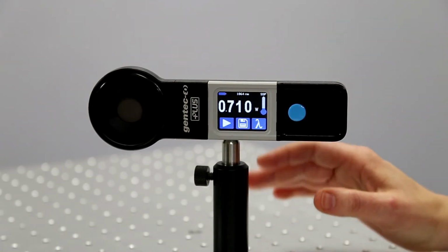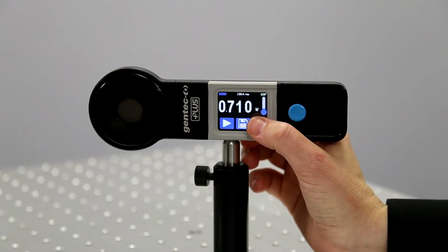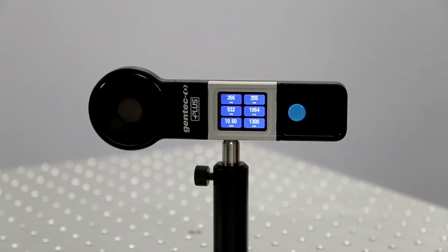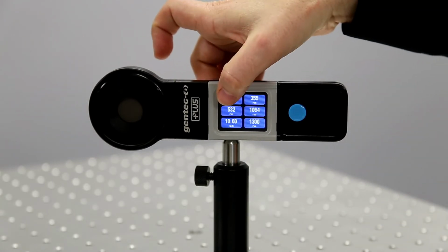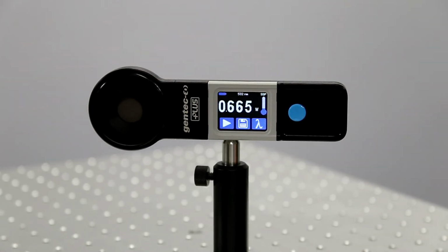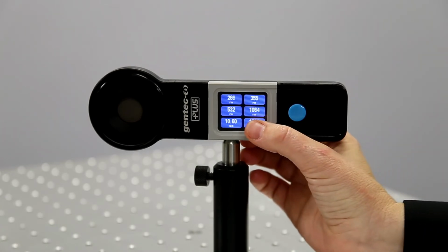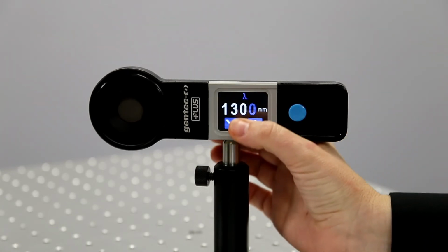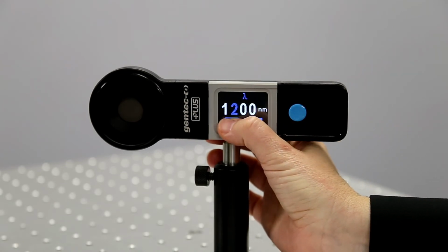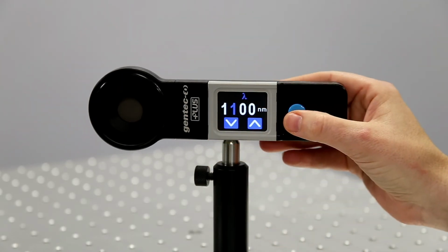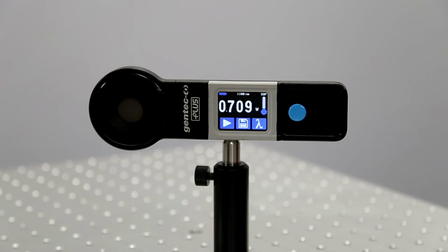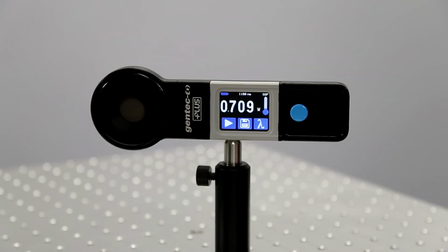To change this, you first tap on the button with the wavelength symbol, which brings you to a screen with 6 preset values. If there's one that you like in there, you can simply press it, and it will change, for example, to 532 nanometers. If you don't have your laser's value in the 6 presets, you can long press on one of the values and then use the arrows to change the wavelength that is displayed. And when you press the blue button, it gets saved to your PRONTO's memory, and that's the wavelength that you're now using. That's all there is to it.